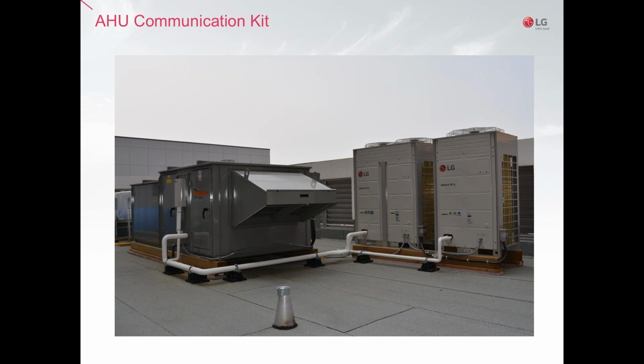This is an example of a system installed by Odell. In this case, you can see that you have two condensers, in this case Multi V 4, connected to a single piping and going to a single coil. You can see in the drawing the EEV kit connected and the controls probably inside. So this unit is going to work like a DOAS, taking 100% outside air. The unit probably has a wheel, so it's recovering part of the heat that is exhausted from the area, and you can have a very efficient unit.